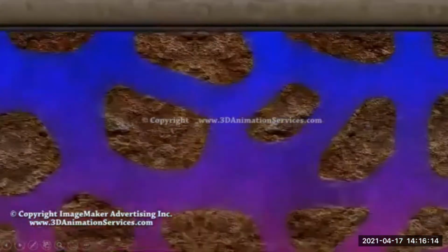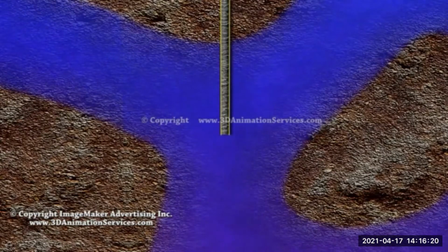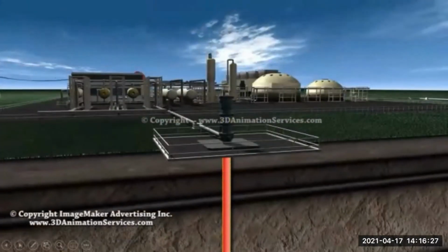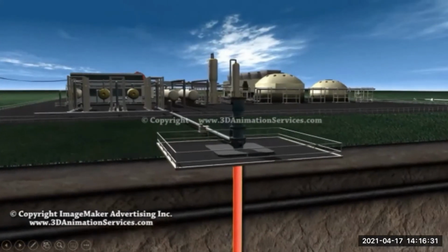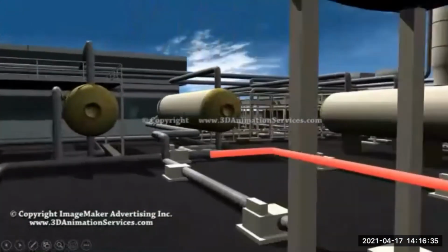Water in underground reservoirs is heated to high temperatures by magma. Production wells drilled up to 10,000 feet below the Earth's surface tap into this hot fluid. Under its own pressure, the fluid flows through these wells toward the surface. As it travels, the pressure lessens, causing a small amount to become steam. Together, the hot fluid and steam move through a surface pipeline to a wellhead separator where the pressure is reduced.